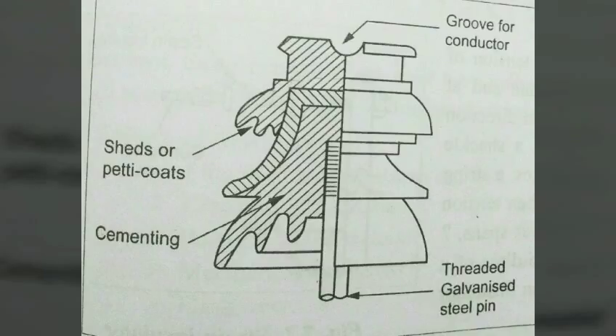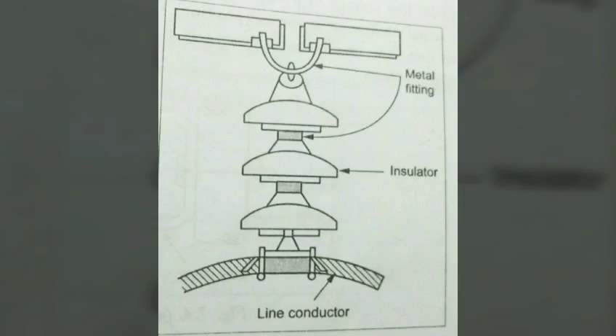Next, suspension type insulators. This type is otherwise called disc or string insulators. As pin type insulators cannot be used for voltages greater than 50 kV, suspension type insulators are used, whose cost is less at high voltages. They consist of a number of porcelain disks connected in series by metal links in the form of a string.